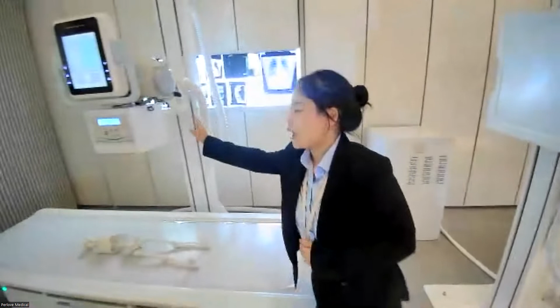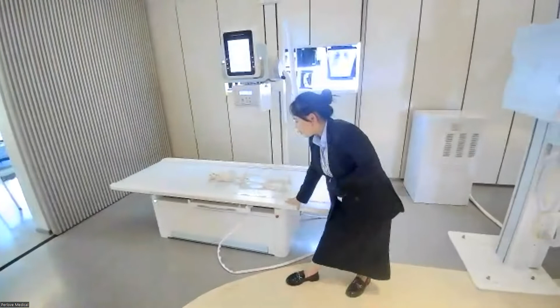It is equipped with our own produced generator and our Canon X-ray tube and the dynamic panel detector and the four floating base and the package stand and the workstation outside the room. Let's introduce it to you one by one. The generator is featured with high output power and a high inverter frequency, 500 kilohertz. If you are familiar with X-ray, you can find that it is one of the highest levels on the market. And for the X-ray tube, this time we cooperate with Canon as well.